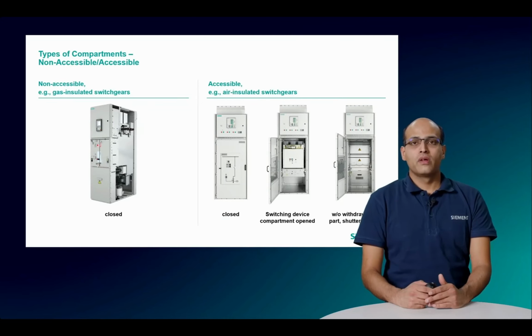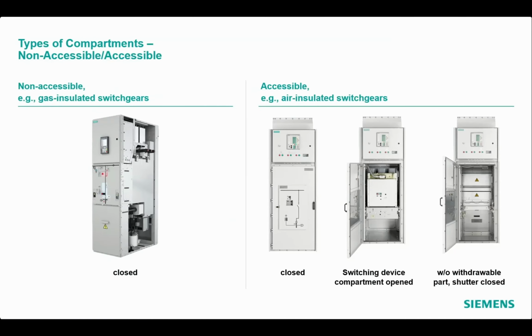As the next topic, we will study the types of compartments. Let us now examine the non-accessible and accessible compartments of a medium voltage switchgear. On the left section, you can see a panel of a gas insulated switchgear. In this panel, the cable compartment at the bottom of the panel is depicted in a closed state. Further up, the closed area in the middle of the panel depicts the gas compartment which contains the switching device. This compartment is filled with gas and sealed for lifetime, meaning that the gas compartment is non-accessible after manufacturing.